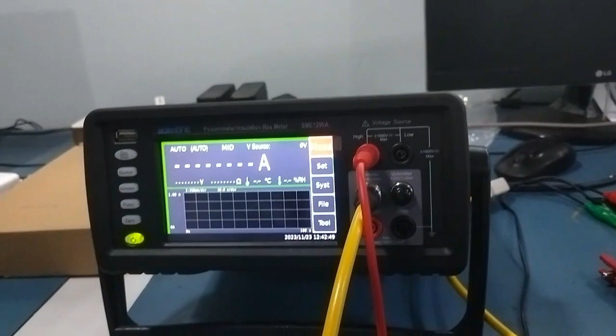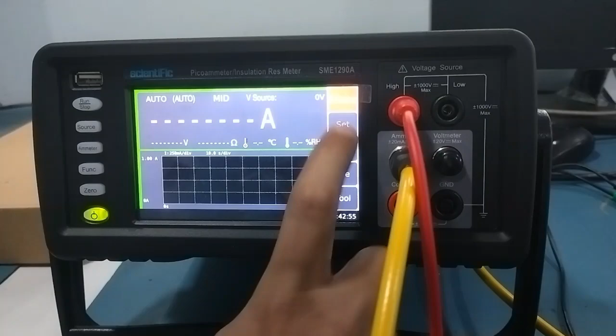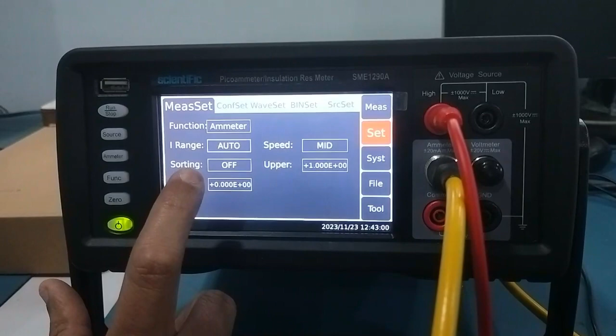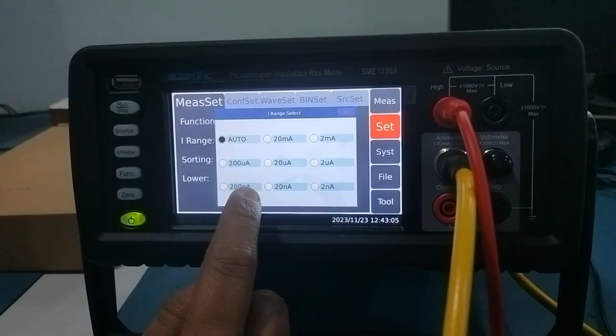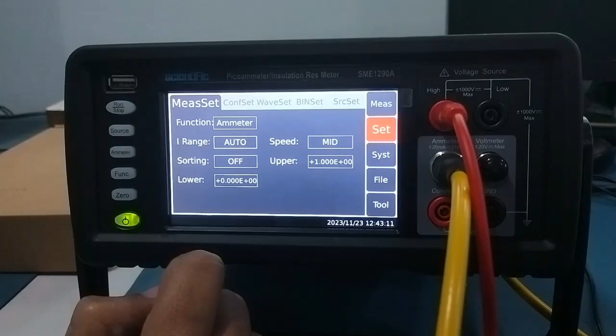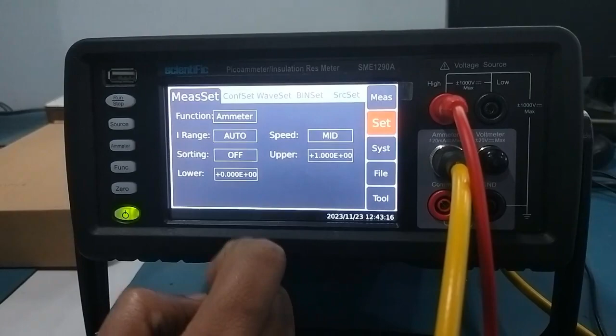After connection, we will set our device for the high resistance measurement. For this we need to press the set button. Here we can see function is set to ammeter. For high resistance measurement we need to keep I range to auto. There are multiple ranges there, 20 milliampere, 2 milliampere. For high resistance measurement we will put it to auto mode. Here we can select the speed fast, medium, slow, so we will keep it at medium.